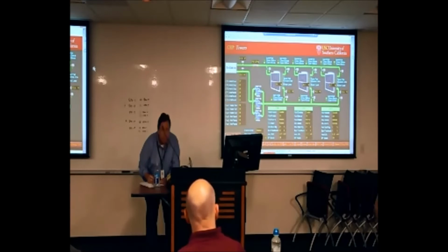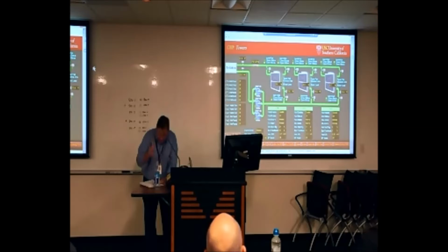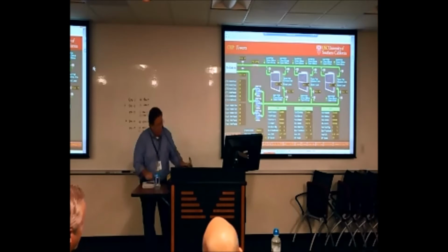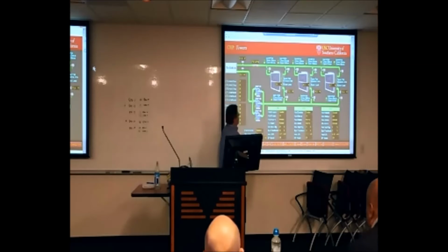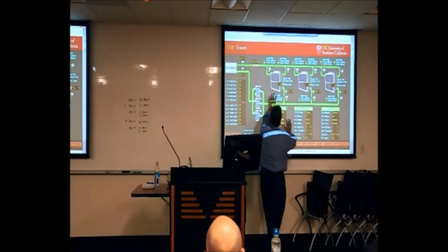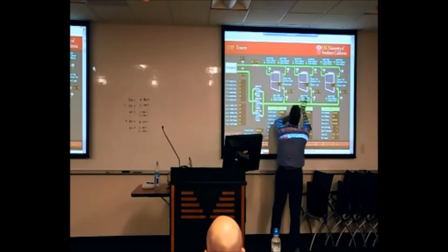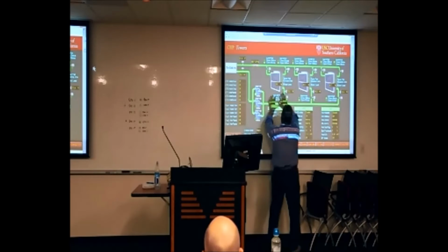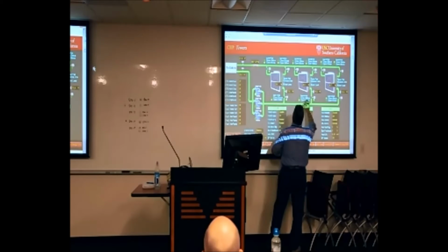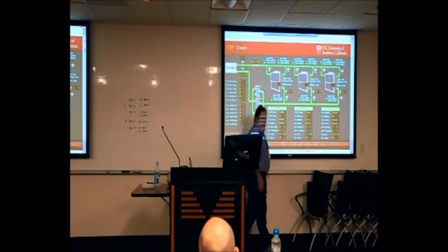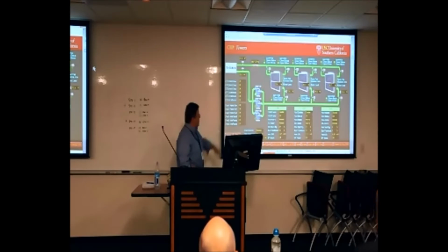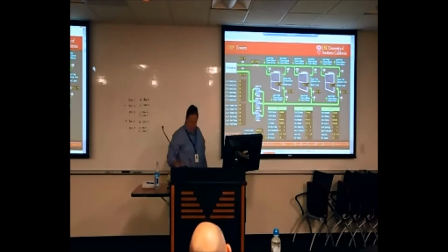Does it run one tower, tower 3, just for backup? No, it runs all 3 towers. Yeah, it runs a lead lag routine. So, for instance, right now, we've only got 2 towers online, and then once a week it's going to do the rotation, and it's going to rotate over to the third tower. So lead, lag 1, lag 2, and then it'll rotate and be lead, lag 1, lag 2, and then every week it's going to rotate like that. So all 3 towers do get usage, and likewise it does the same thing on the pumps. Is that rotation on a time schedule? It's on a time schedule, yes, yes.